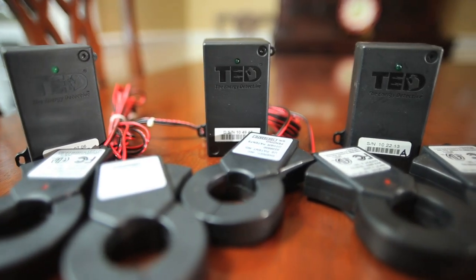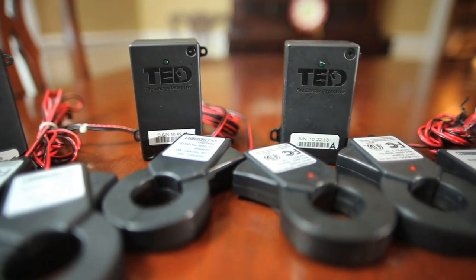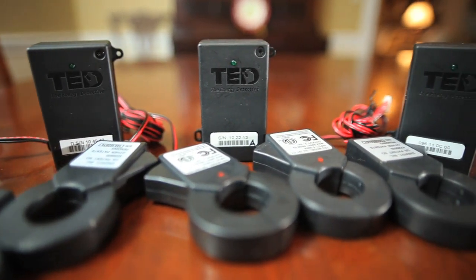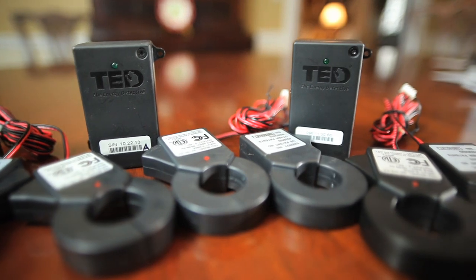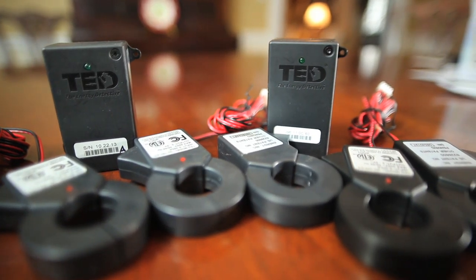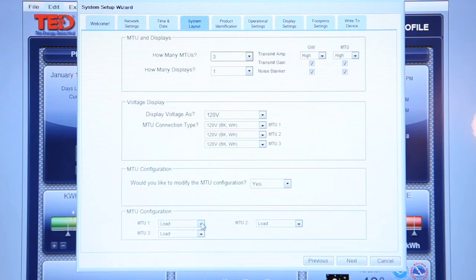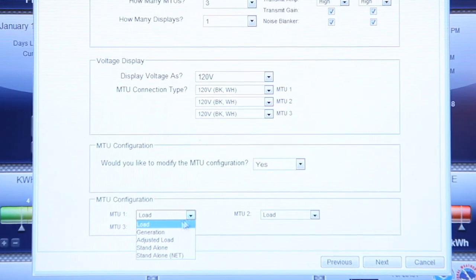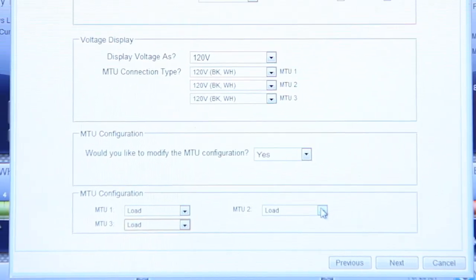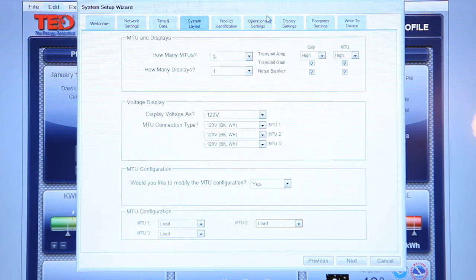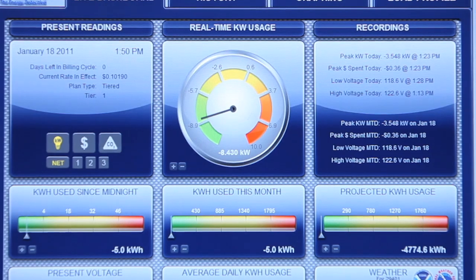These procedures can be used with up to four different MTU and CT sets. Keep in mind that the gateway can only hold up to four MTU and CT sets, since they run on four different frequencies. If you have three main panels, you would connect an MTU CT set to each main panel. On our Footprint software, we will change all three MTU readings to say load. Once you write your device, you will see each breaker panel individually on the Footprint dashboard, as well as a net reading of all of your data. Thank you again for purchasing our product. We hope you enjoyed using your TED system.